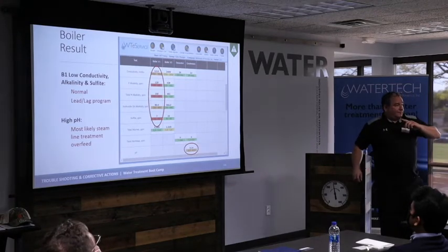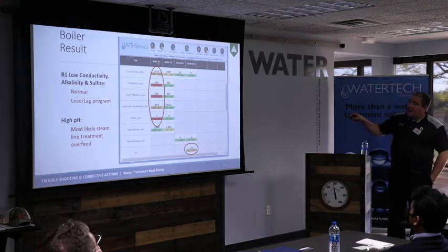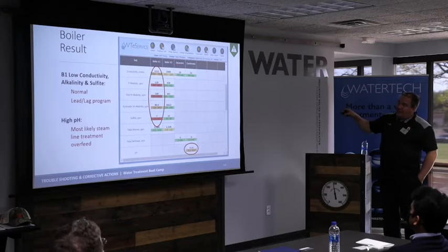All right? Does it kind of make sense? You see when we were talking? Or the other argument would be, what if this wasn't a lead-lag? Well, what could happen is this boiler is losing water, not cycling up. But at the same time, the boiler that is running all the time seems to be fine.